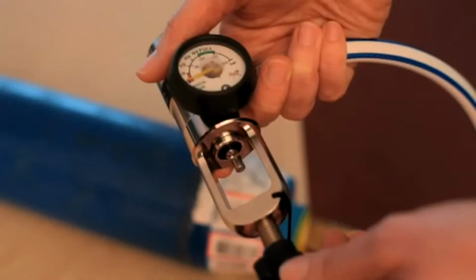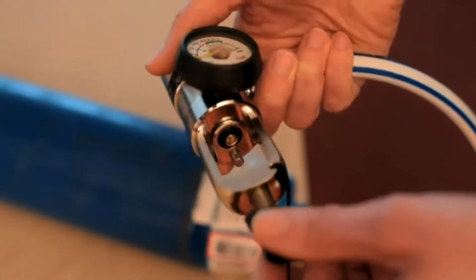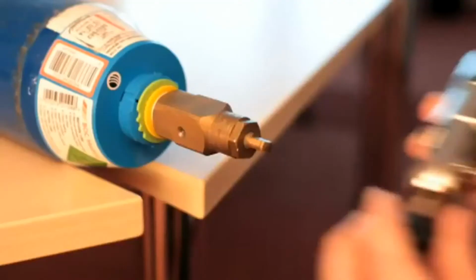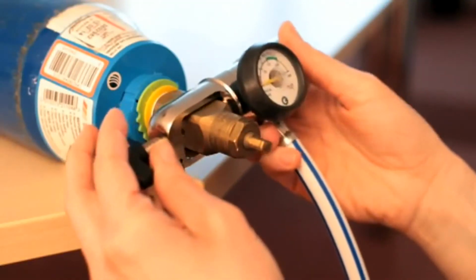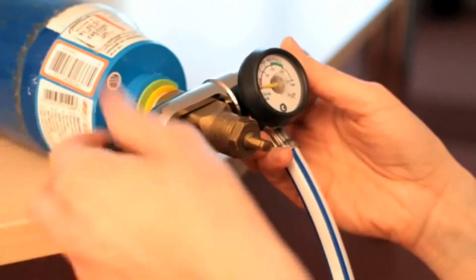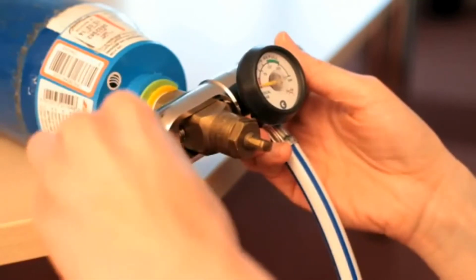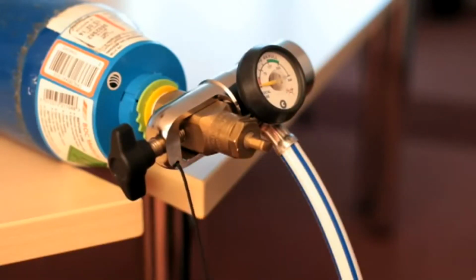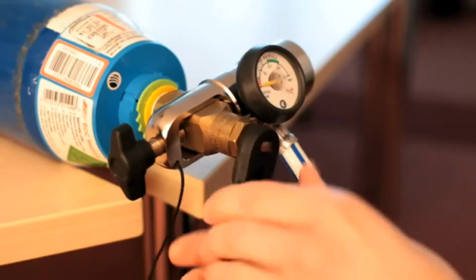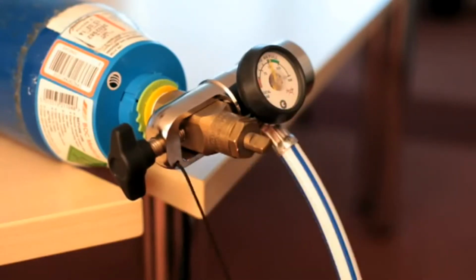Check that the cylinder valve connection and inlet O-ring are clean and in a good condition. Attach the regulator to the cylinder and tighten the yoke firmly by hand. Turn on the cylinder valve slowly. Check that the contents gauge points to a green or white part of the dial. If there is insufficient gas for treatment, replace the cylinder.